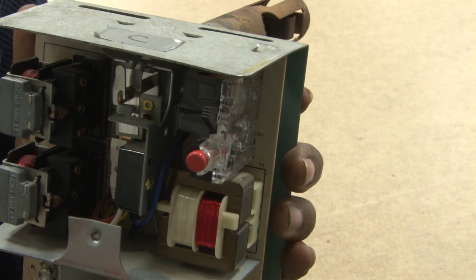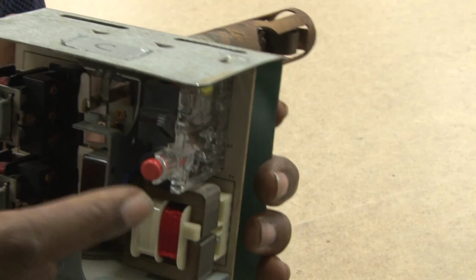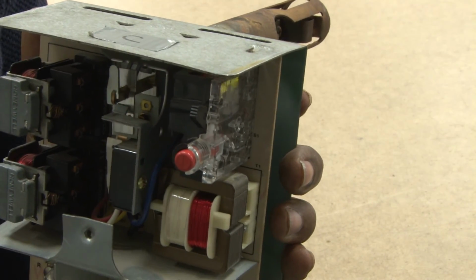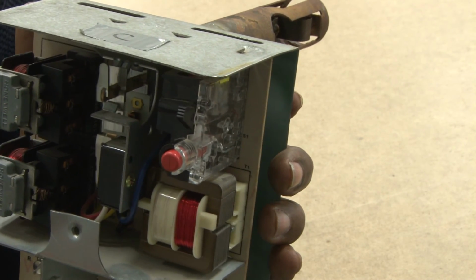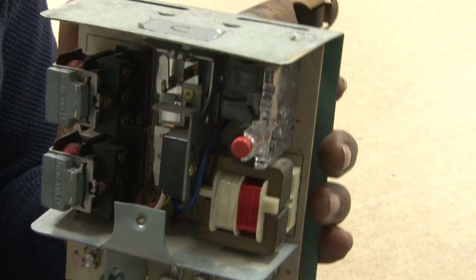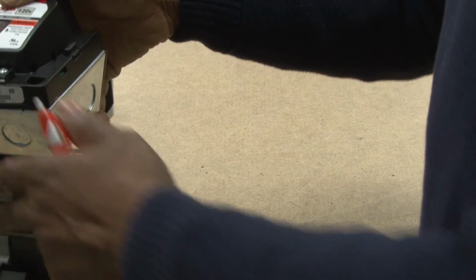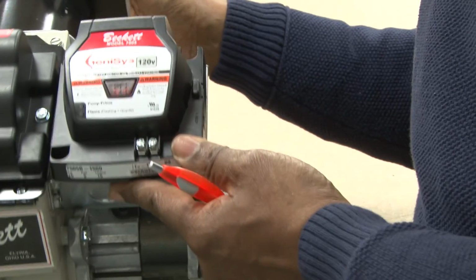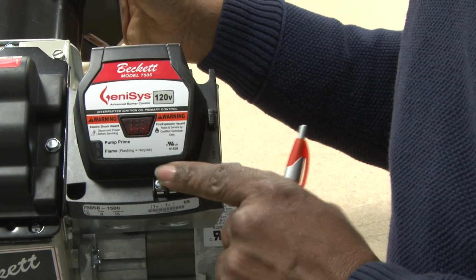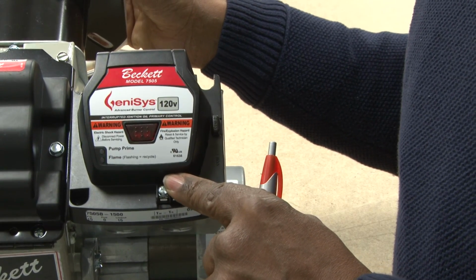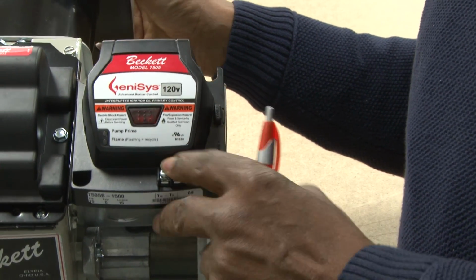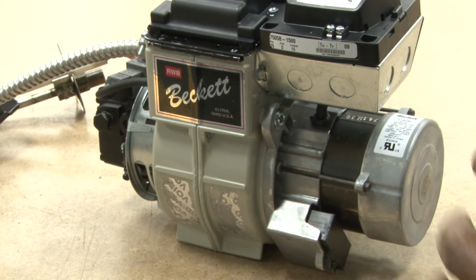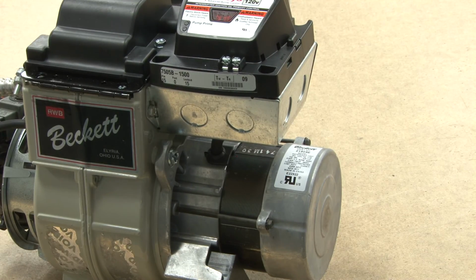which needs to be manually reset by this button here. One of the problems was that sometimes a homeowner would come back and keep resetting it, and they could actually put additional raw oil inside the combustion chamber, which wasn't very safe. The newer styles these days use electronic circuitry, the small circuitry right here, all solid state, and use a CAD cell to sense the flame to cause it to operate. So these days it is a lot more efficient than it used to be years ago.